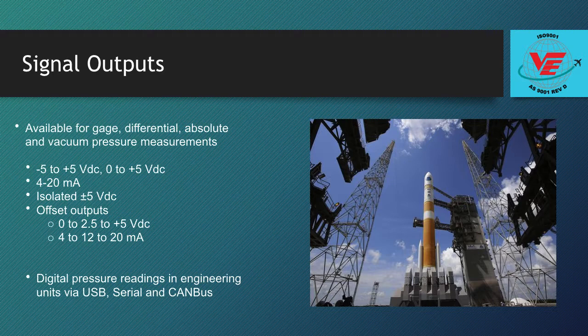The P895 is available with the most commonly specified output signals. The standard output is 0 to 5 volts DC over the full-scale pressure range. Offset voltage options and voltage outputs isolated from the power supply are also available. The P895 can be ordered with a 4 to 20 milliamp output and an offset 4 to 12 to 20 milliamp output. The P895 can be powered by any unregulated DC power supply that puts out plus 9 to plus 55 volts DC at 20 milliamps or more.